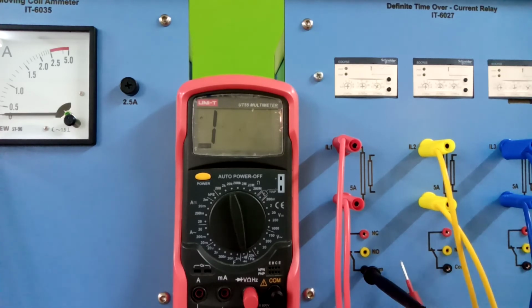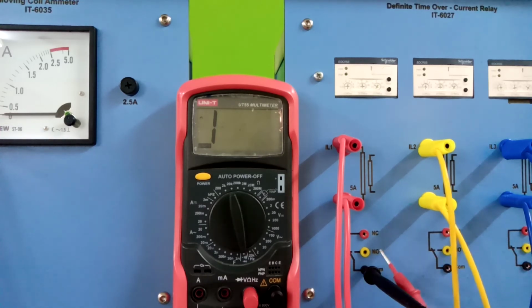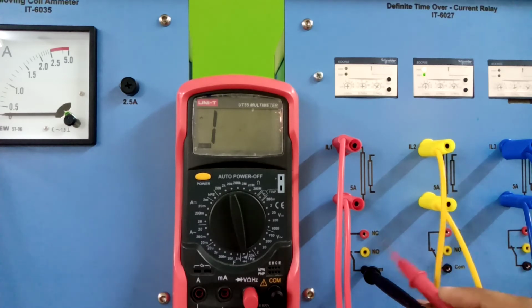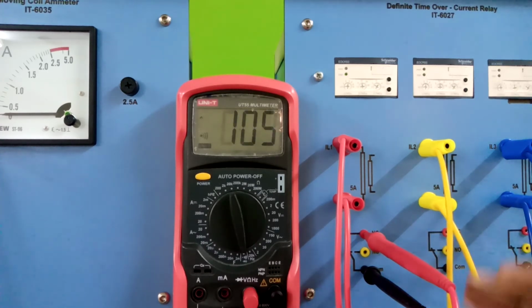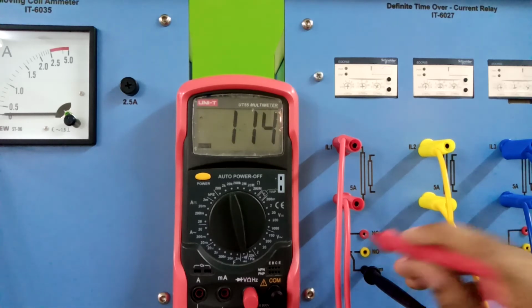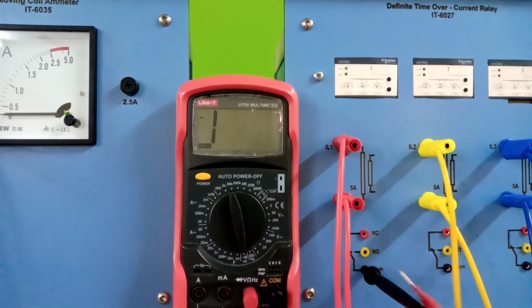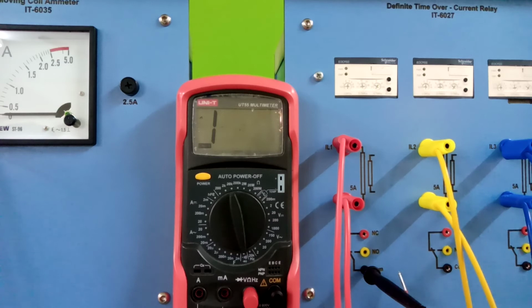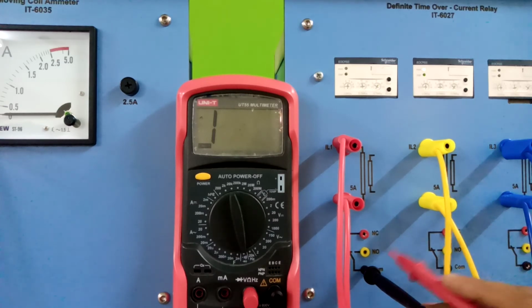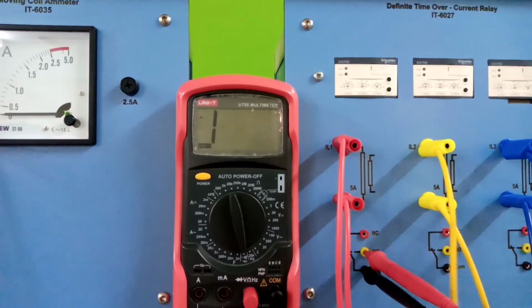Now how can you utilize this? You can connect these terminals to your power relay, which we are going to connect, and then you will see that when there is normal operation, the connection will be continued. But when the operation is under a short circuit or over the range, like we have set 0.5 range, then you will see that these two connections will be opened. So let's start with the normally open. So here you go. For the normally open, right now no beep, normally open.